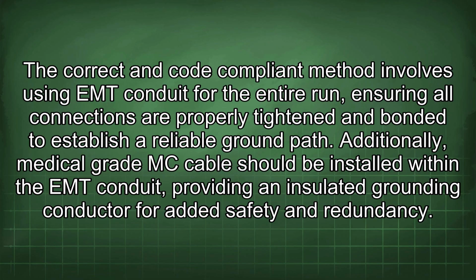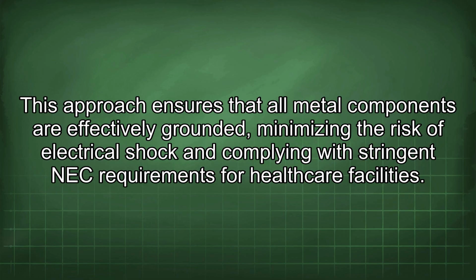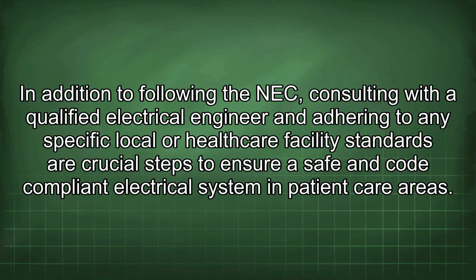The correct and code-compliant method involves using EMT conduit for the entire run, ensuring all connections are properly tightened and bonded to establish a reliable ground path. Additionally, medical-grade MC cable should be installed within the EMT conduit, providing an insulated grounding conductor for added safety and redundancy. This approach ensures that all metal components are effectively grounded, minimizing the risk of electrical shock and complying with stringent NEC requirements for healthcare facilities. In addition to following the NEC, consulting with a qualified electrical engineer and adhering to any specific local or healthcare facility standards are crucial steps to ensure a safe and code-compliant electrical system in patient care areas.